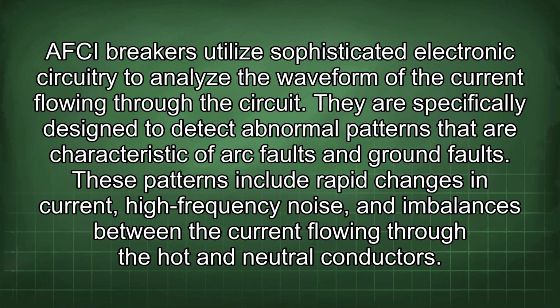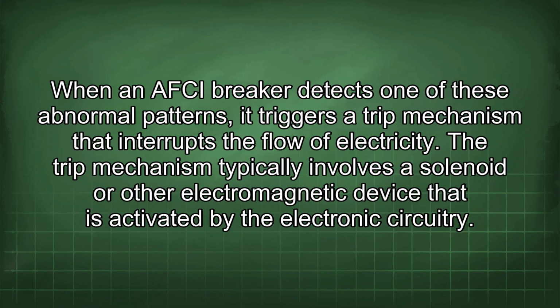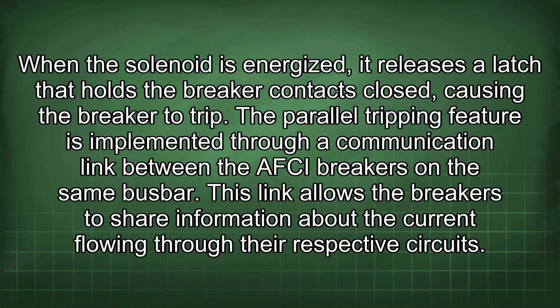AFCI breakers utilize sophisticated electronic circuitry to analyze the waveform of the current flowing through the circuit. They are specifically designed to detect abnormal patterns that are characteristic of arc faults and ground faults. These patterns include rapid changes in current, high-frequency noise, and imbalances between the current flowing through the hot and neutral conductors. When an AFCI breaker detects one of these abnormal patterns, it triggers a trip mechanism that interrupts the flow of electricity. The trip mechanism typically involves a solenoid or other electromagnetic device that is activated by the electronic circuitry. When the solenoid is energized, it releases a latch that holds the breaker contacts closed, causing the breaker to trip.